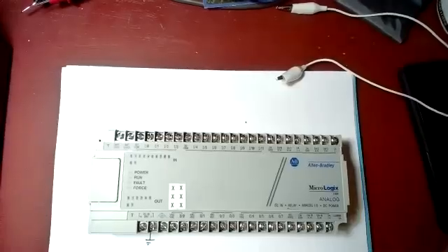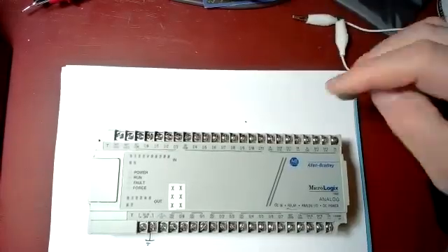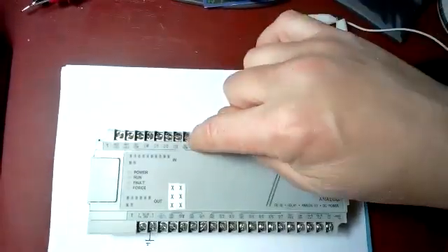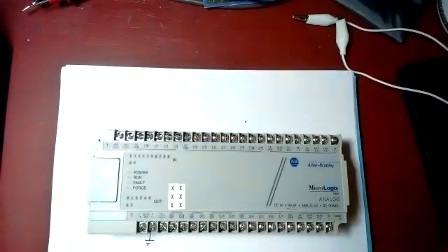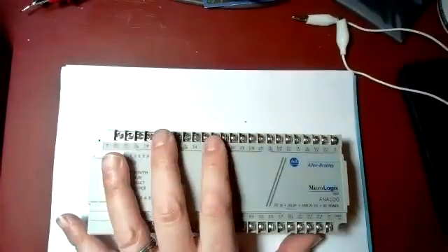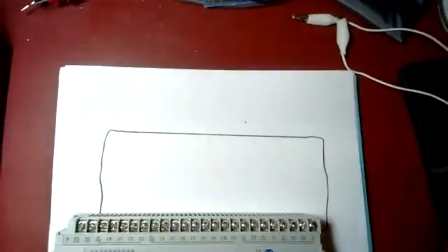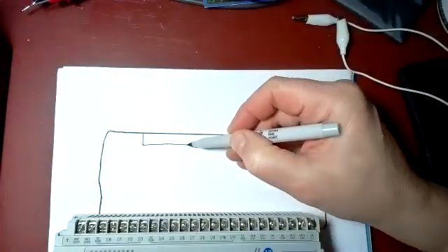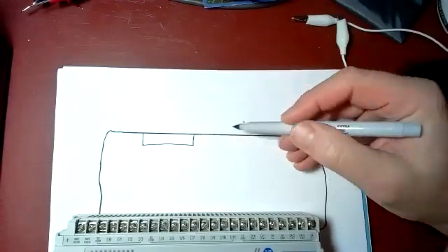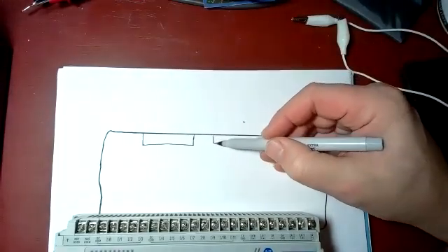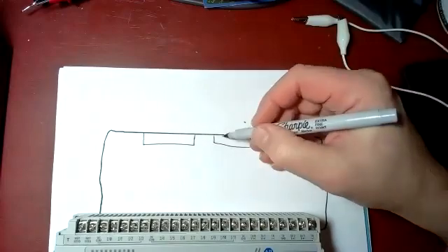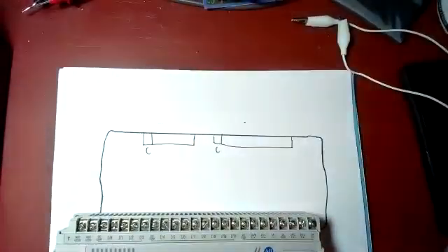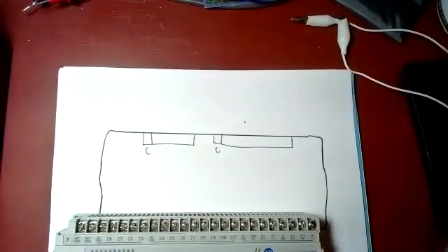So you might ask me, why do I have multiple comms and then a group of inputs associated with one comm and another group of inputs associated with other comm? And that's because I may have separate ways of wiring in sensors. I may have one group of sensors that I need to wire up NPN, and the other group would be PNP. So that common associated with it can have two separate ways of being wired up.